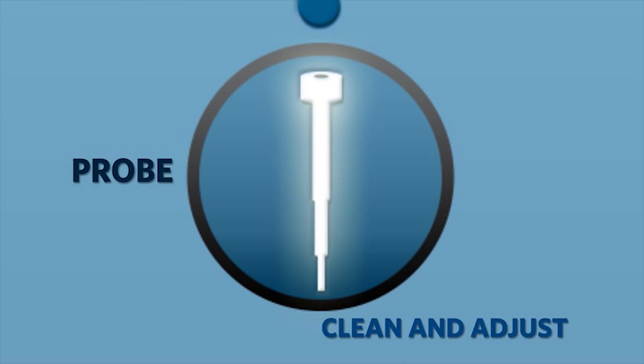Cleaning the sample probe is the last step in basic troubleshooting. It includes sonicating and/or flushing the sample probe, adjusting the sample probe height, then running a system clean. This step requires a calibration verification once completed.